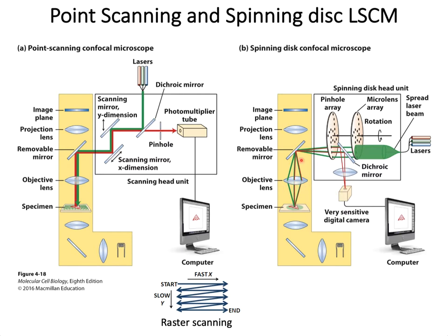The fluorescence emitted from all these points passes back through the objective lens and through the holes in the spinning disk and is then bounced off a dichroic mirror into the sensitive digital camera. The pinholes in the disk are arranged so that as it spins, it rapidly illuminates all parts of the specimen several times.